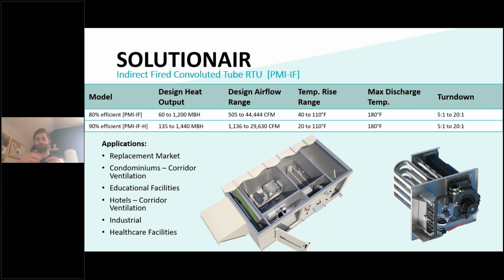The other reason to go with this is typically the footprint will be different than the drum and tube. The drum and tube will be a little thicker, so a little wider, and the convoluted tube will be a little stretched, so a little longer and skinnier. You see the turn down ratio is varying on these units.